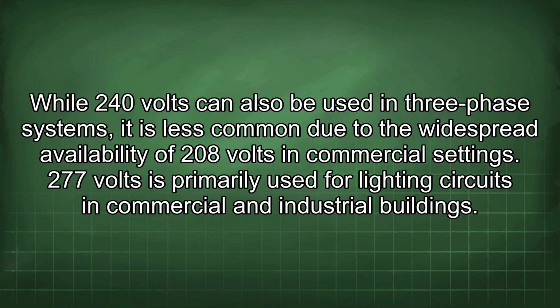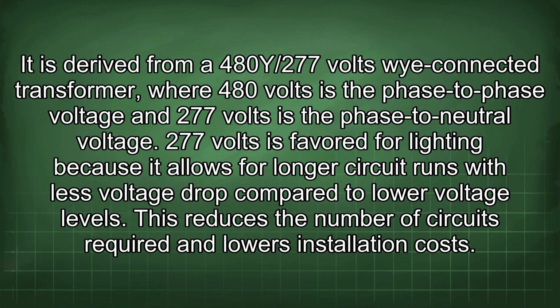277 volts is primarily used for lighting circuits in commercial and industrial buildings. It is derived from a 480Y/277 volts Y-connected transformer, where 480 volts is the phase-to-phase voltage and 277 volts is the phase-to-neutral voltage. 277 volts is favored for lighting because it allows for longer circuit runs with less voltage drop compared to lower voltage levels. This reduces the number of circuits required and lowers installation costs.